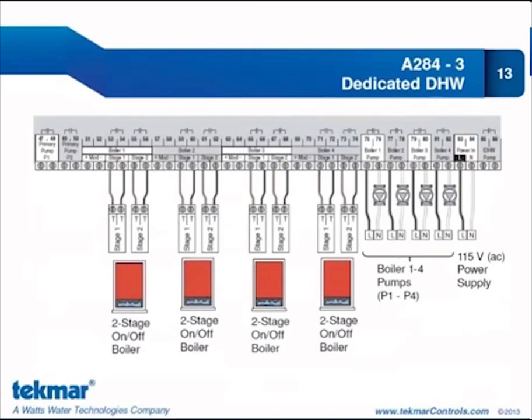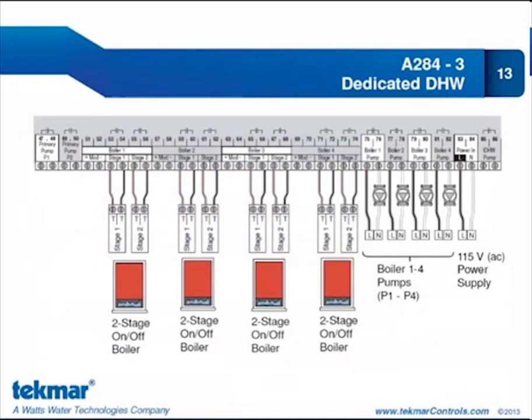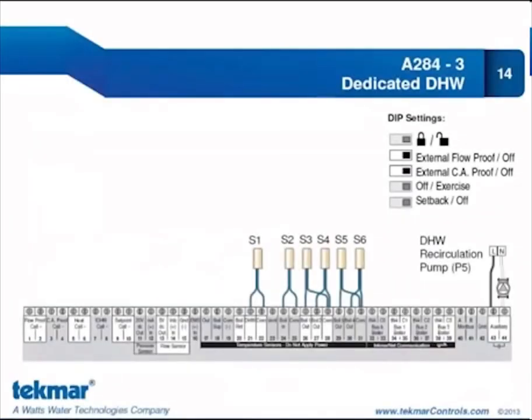Taking a look at the bottom half of the control for application 3, it's certainly one of our simpler installations. The primary pump terminals are both empty since we have no primary pumps to control. We have four boiler banks, connecting stage 1 and stage 2 terminals to the stage 1 and stage 2 TT contacts on each two-stage on-off boiler. We also have a boiler pump for each of our four boilers, and 115V power in. The top half is even more simple — we have sensors for domestic hot water, boiler inlet, and individual boiler outlet sensors, and the auxiliary relay is being used to control the domestic hot water recirculation pump.